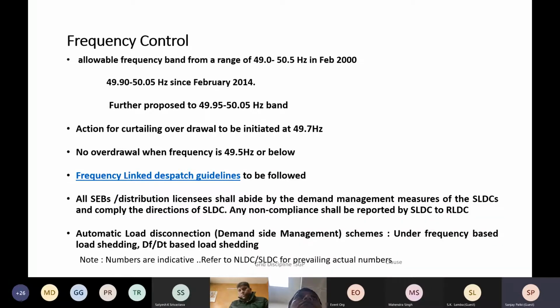Further, you must have read the recent news that automatic generation control, which was piloted earlier, has now been inaugurated at the National Load Dispatch Center. So apart from automatic load control by way of load shedding schemes, the under frequency load shedding scheme or df/dt load shedding scheme, there is now also automatic generation control available. And this has basically become an enabling provision to narrow down the frequency band.